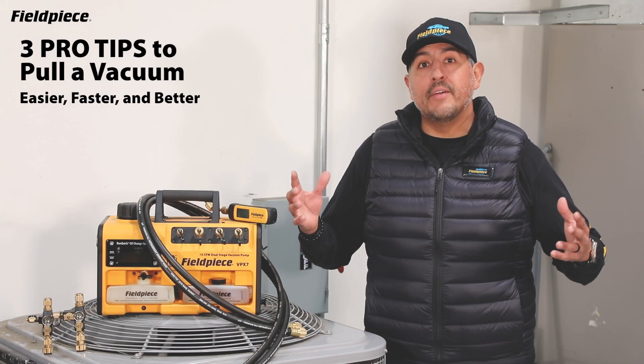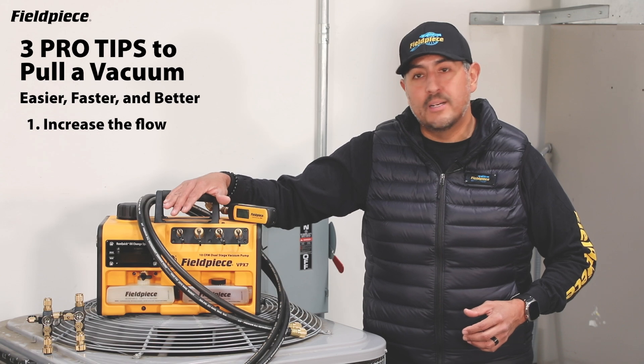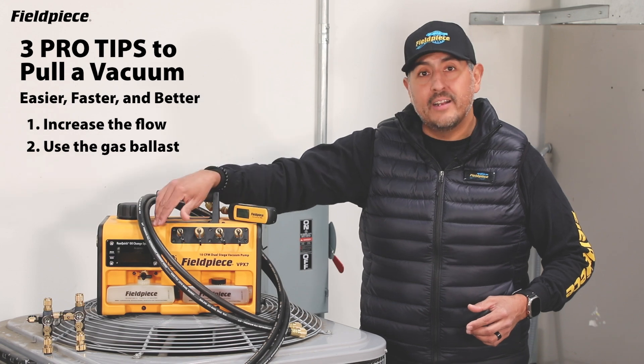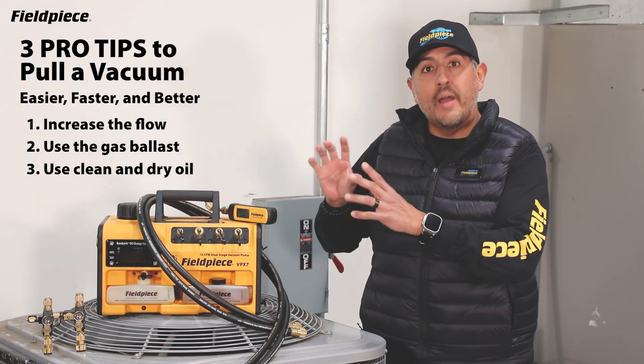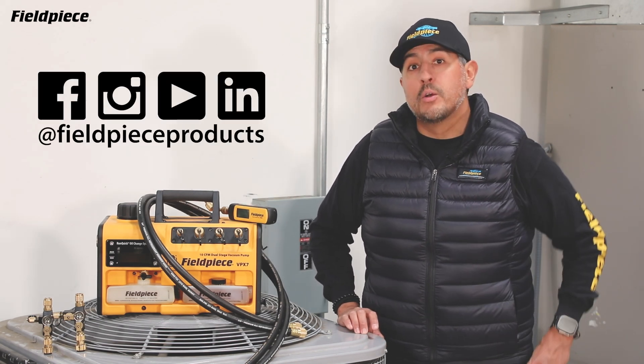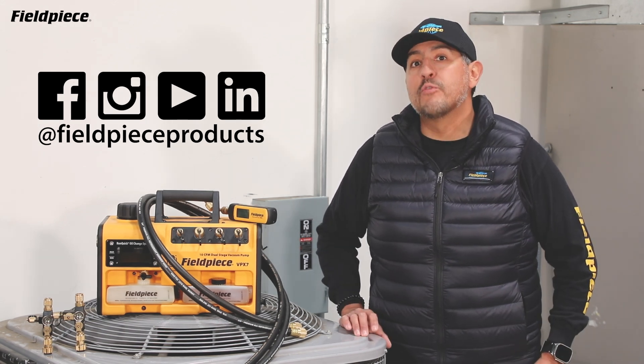And there you have it. Implementing these pro tips — like increasing flow by removing Schrader valves and connecting your pump directly to the system using larger diameter vacuum rated hoses, along with using the gas ballast to extend the life of your vacuum pump oil and making sure you have clean dry oil in your vacuum pump — will help you pull a vacuum easier, faster, and better. For more information, go to fieldpiece.com. Follow us on social media at fieldpieceproducts, and as always, stay tuned for more videos.